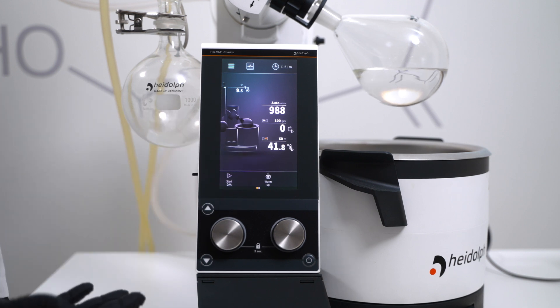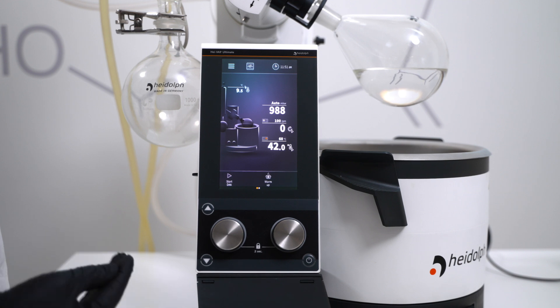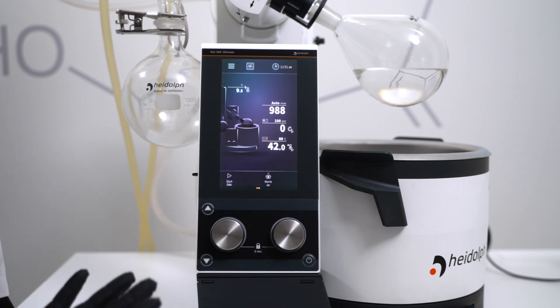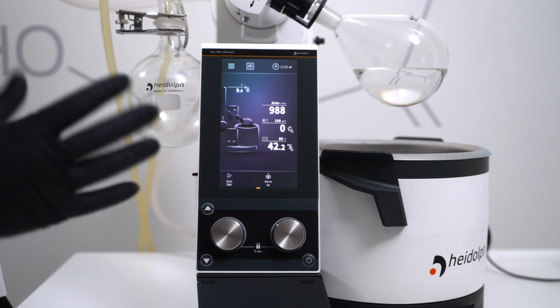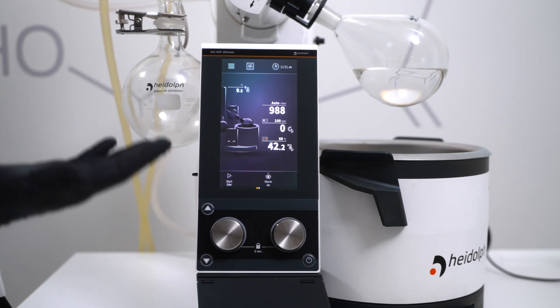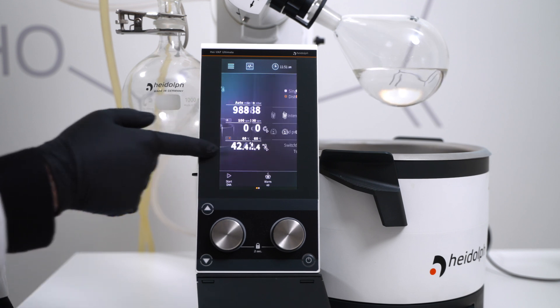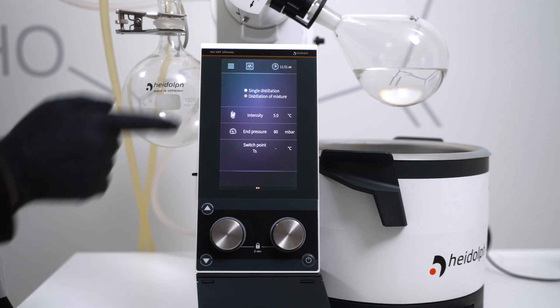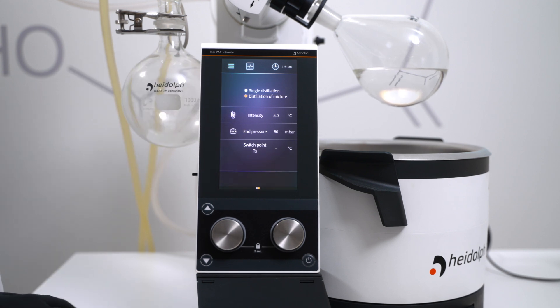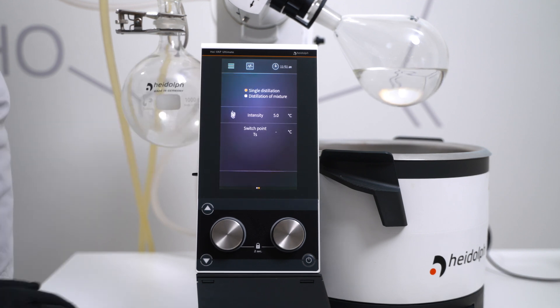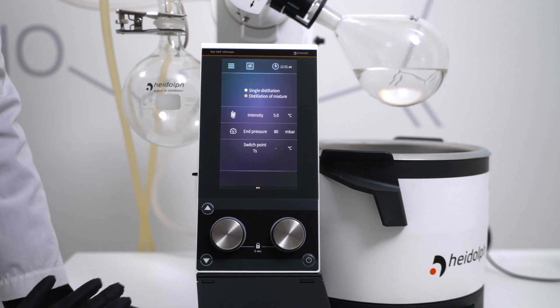What's nice about DAA is that you don't have to pre-warm your bath in order to make it work. I generally recommend preheating it as you're waiting for your chiller to pull down anyway, but the system will automatically adjust its parameters as that heating bath heats up. After we've looked at those parameters, we're going to slide to the right, and we have two options: single distillation and distillation of mixture. Single distillation is for evaporating a single solvent. Distillation of mixture is for evaporating multiple solvents.